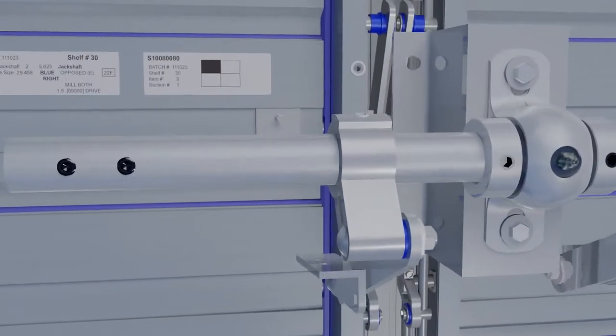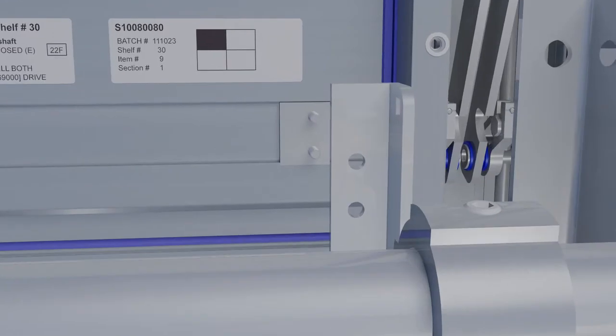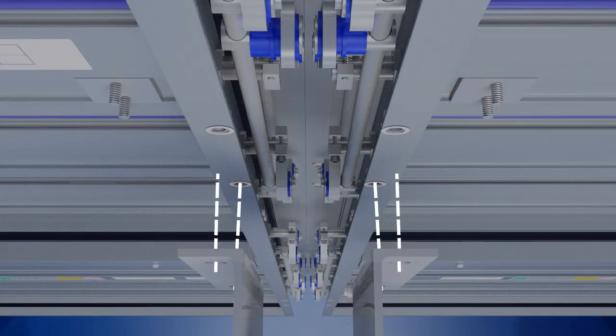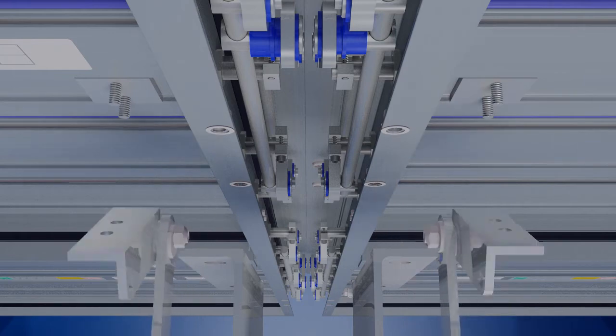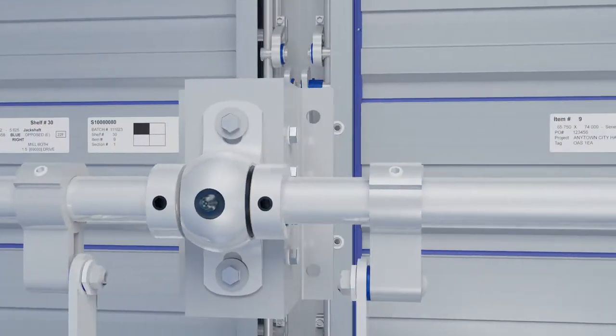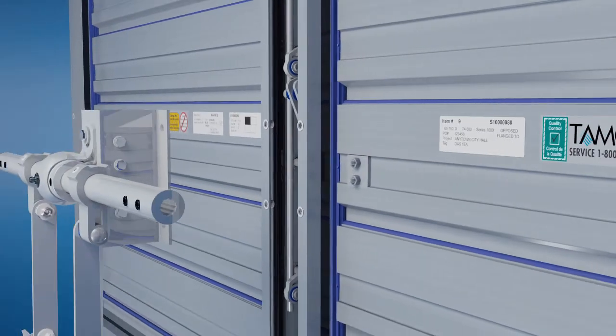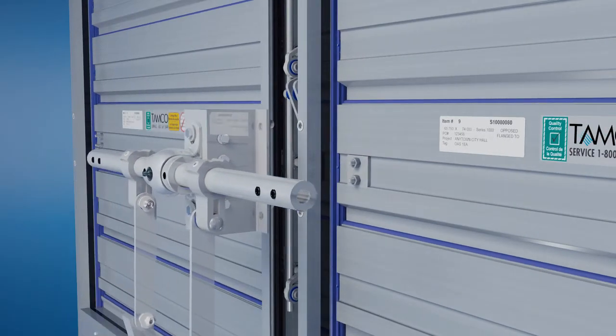First, place the bridge bracket assembly so that the holes in the bridge bracket align with all four pre-drilled holes on the damper frames where the two sections meet. Attach the bridge bracket assembly to the damper frames using the factory provided 1/4-inch bolts. The bolts are located on the side of the bridge bracket for transportation purposes.